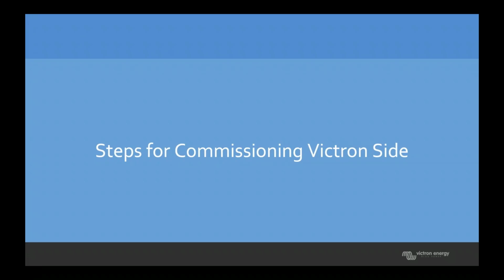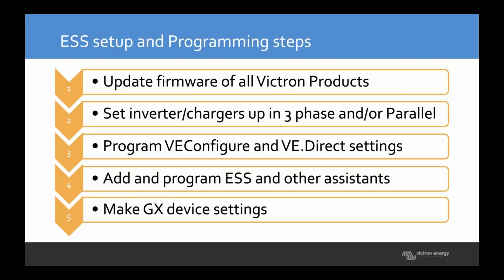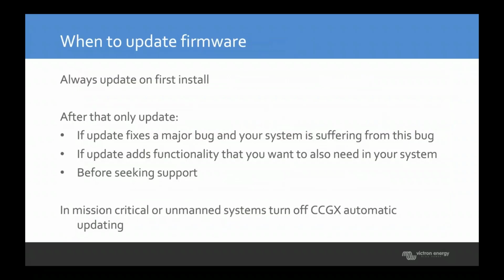So now I'm quickly going to run through some steps for commissioning on the Victron side. Firstly, update the firmware of all Victron products. You should always update firmware on a first run. We fix bugs in firmware quite regularly and improve system performance. However, once the system is running and stable, you shouldn't update firmware. It shouldn't be required.